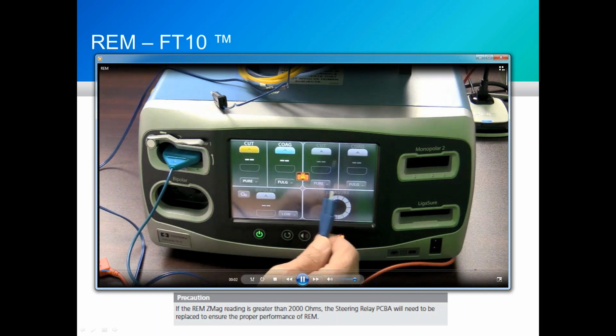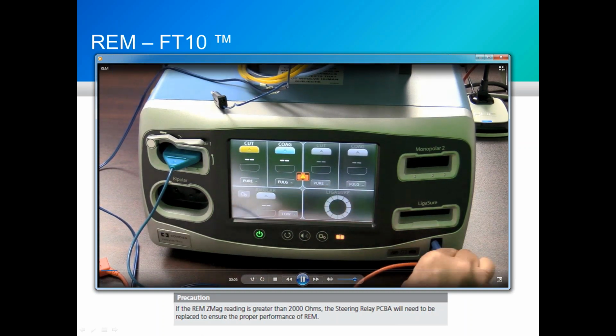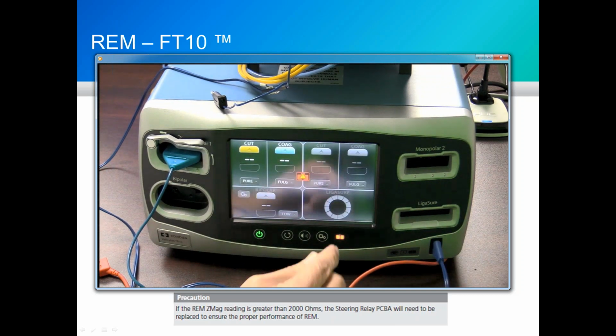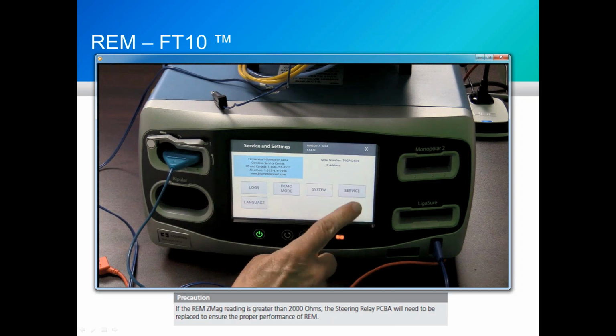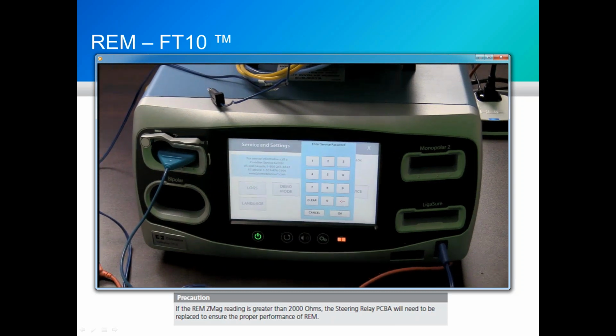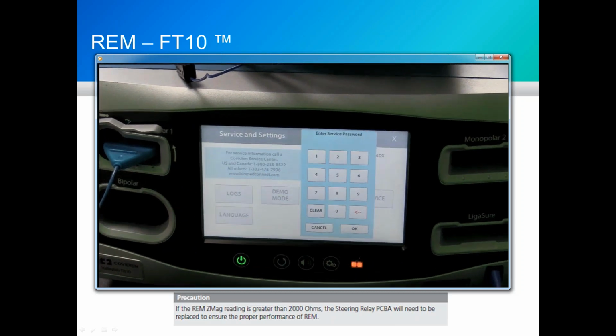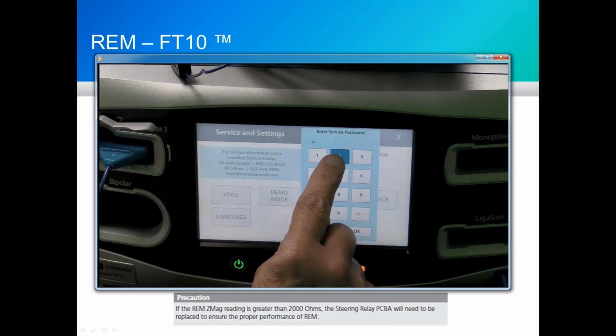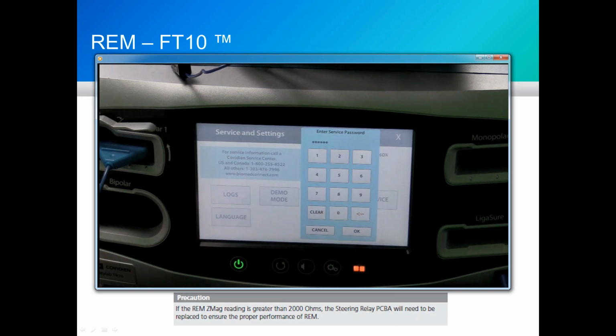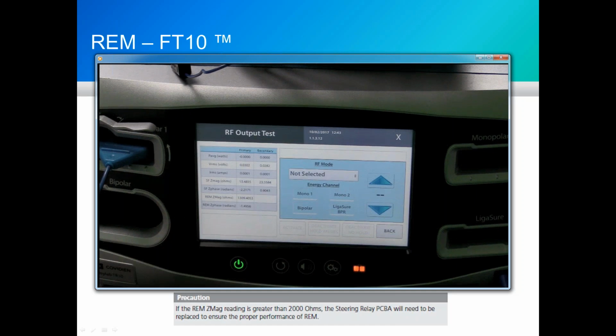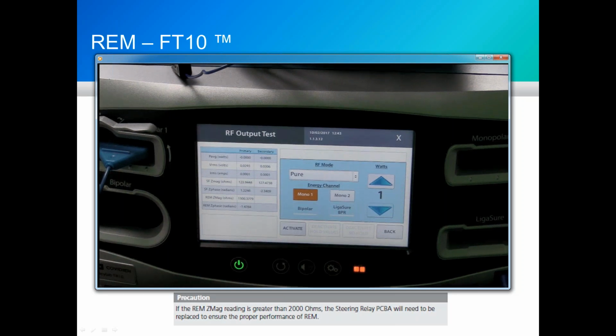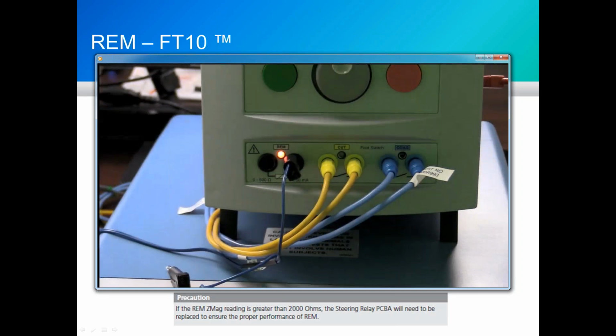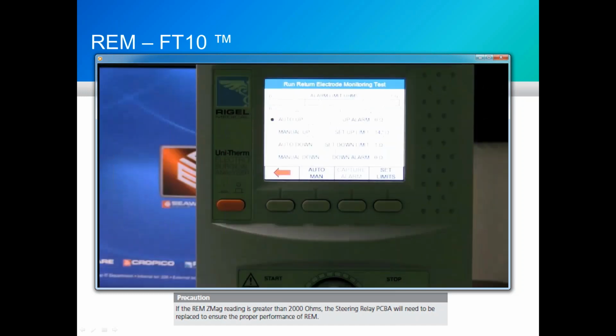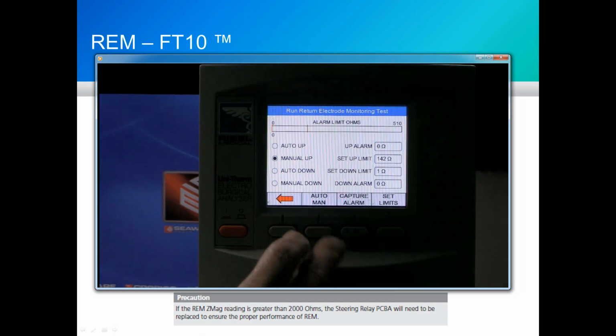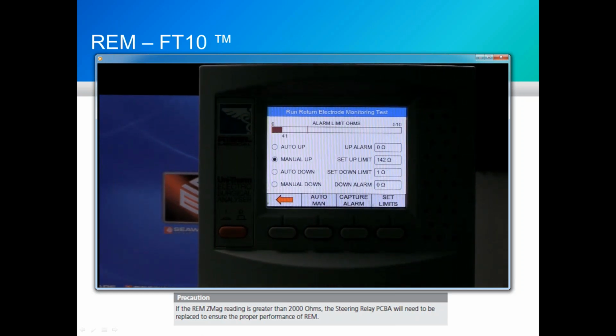So we'll be using videos for a number of our demonstrations today. To test the REM function, you use the REM cable with the clear plastic pin on the portion that goes into the unit. We're going to go into service mode and enter in the password 423213. RF output test. We're going to select pure for monopolar. We're going to pan up now to the display on the Unitherm. Notice that I have not connected both banana jacks to the REM output. The FT10 is going out and interrogating the resistance at about 70 Hertz.